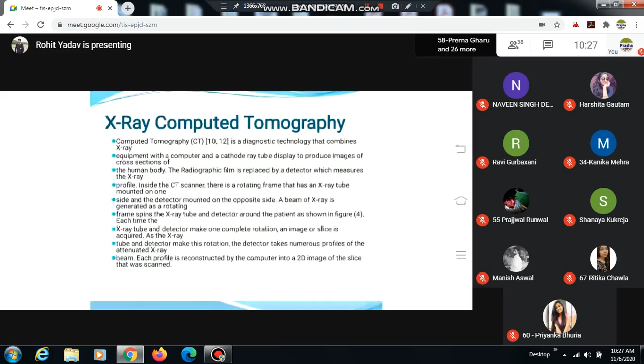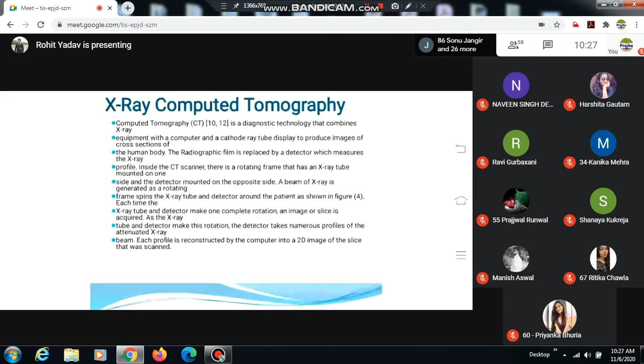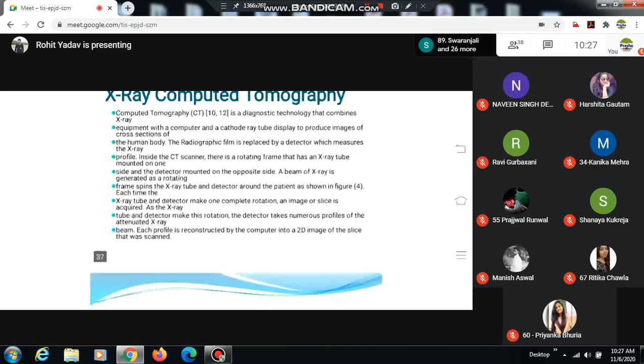With time, the X-ray tube and detector make one complete rotation and an image or slice is acquired. As the X-ray tube and detector make this rotation, the detector takes numerous profiles of the attenuated X-ray beam. Each profile is reconstructed by the computer into a 2D image of the slice that was scanned. 3D CT can be obtained by spiral CT. Spiral CT acquires a volume of data with the patient anatomy all in one position. This volume data set can then be computer reconstructed to provide a three-dimensional image of complex structures.